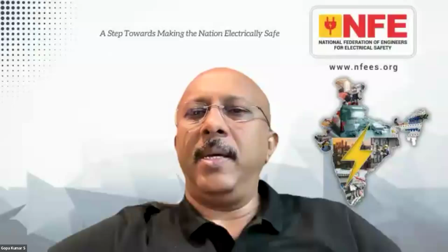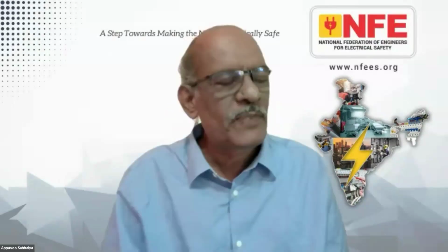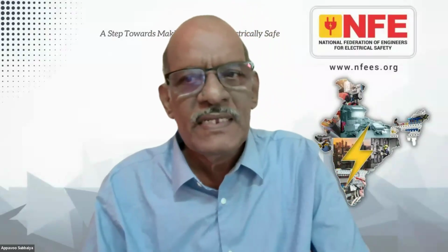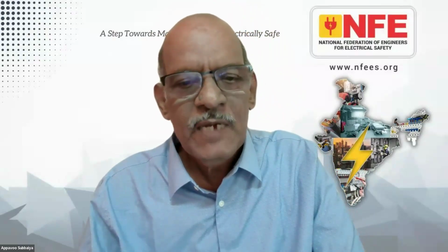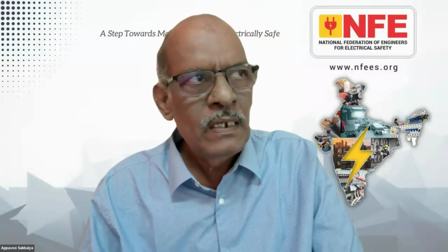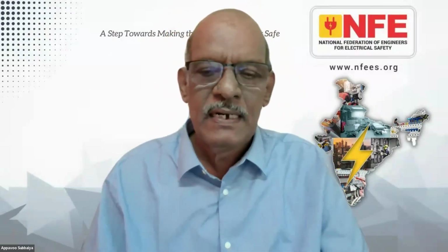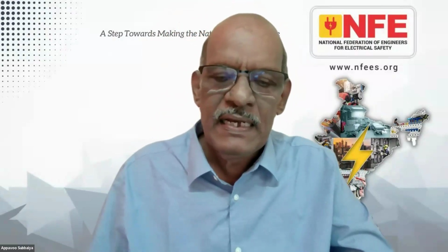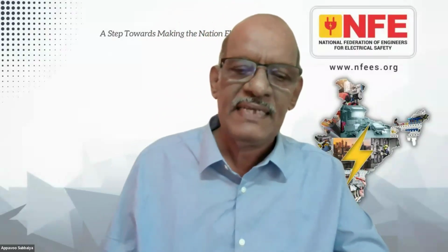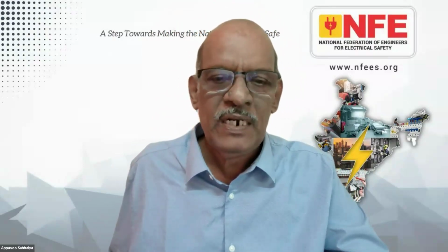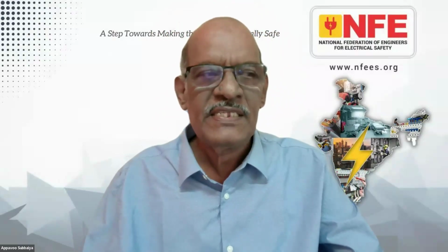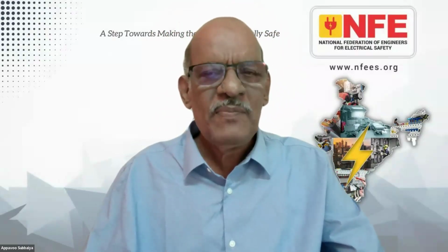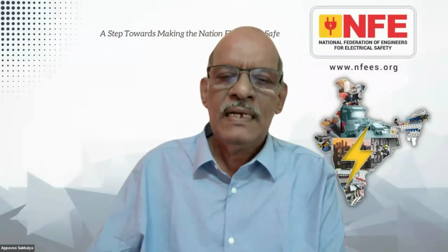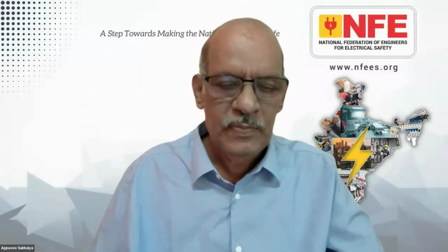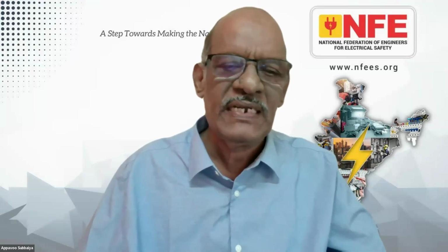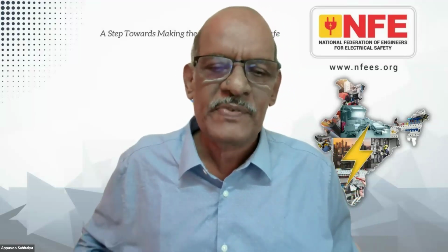Thank you. I would like to supplement that. The question was about the primary cable from the substation up to the transformer. For the fault loop impedance, if there is a secondary LV overhead line, then there is a provision for busbar, cable, overhead line, everything, in IEC 60909 Part 2. For the primary side, only the fault level calculation will apply. That is not a major issue. You can assume an infinite fault level of the substation.